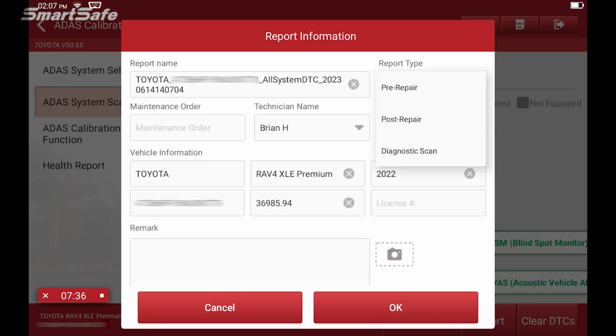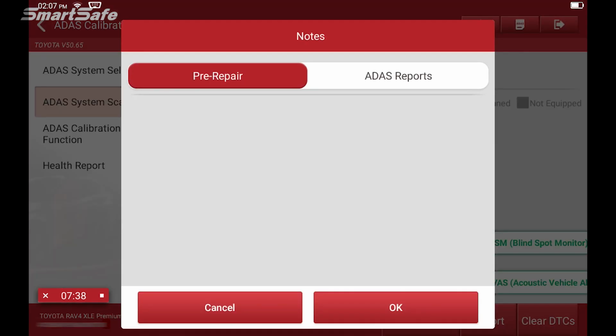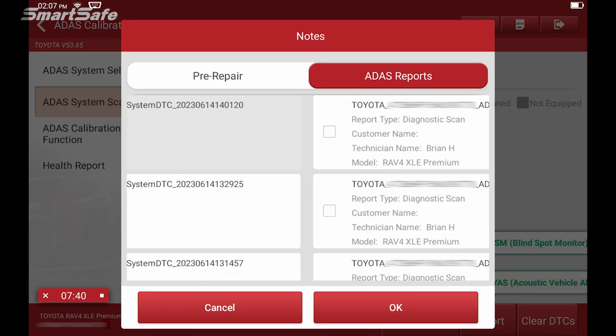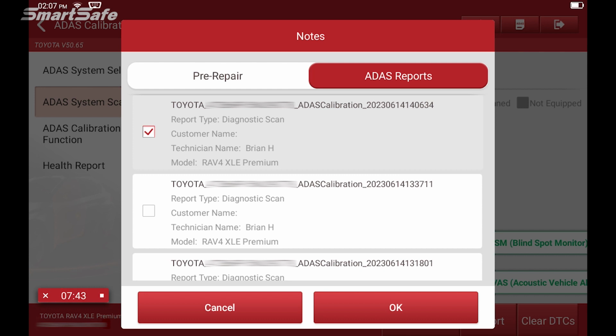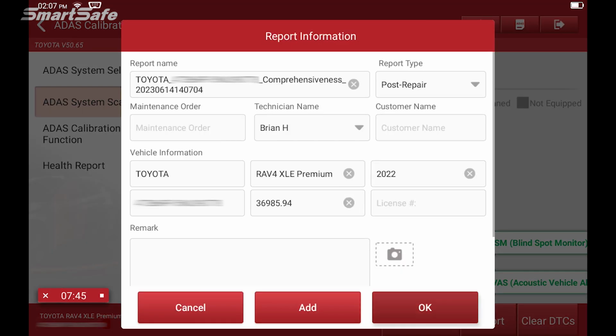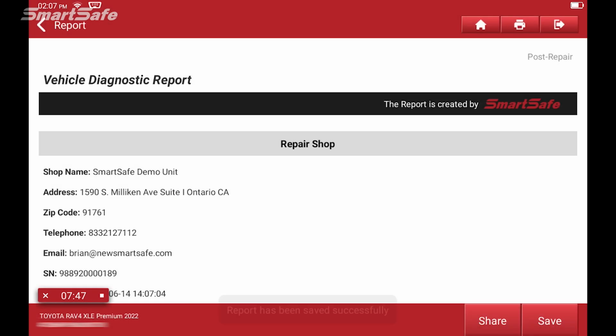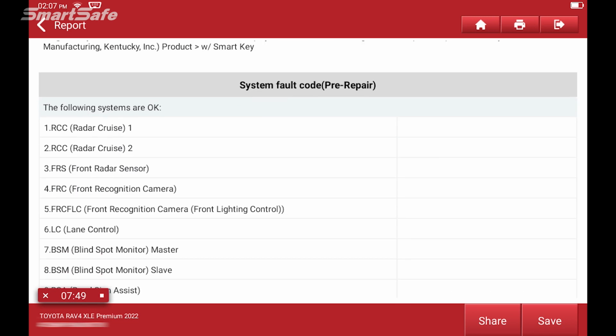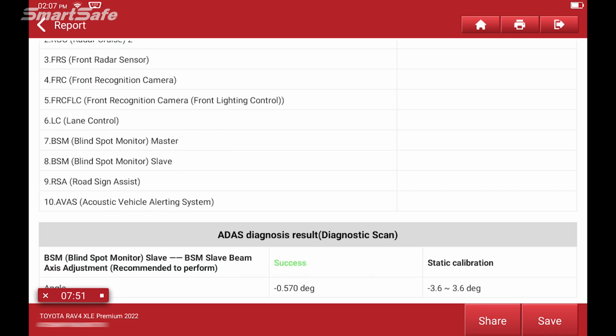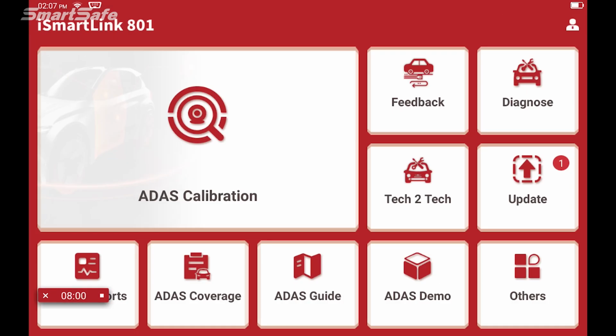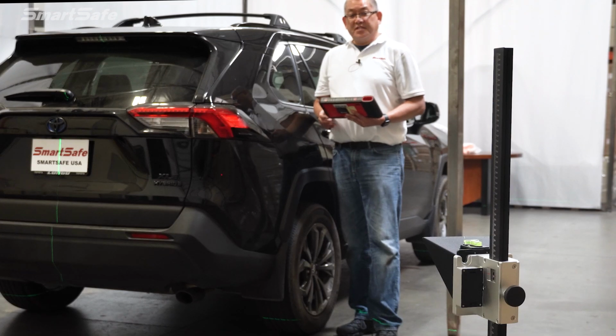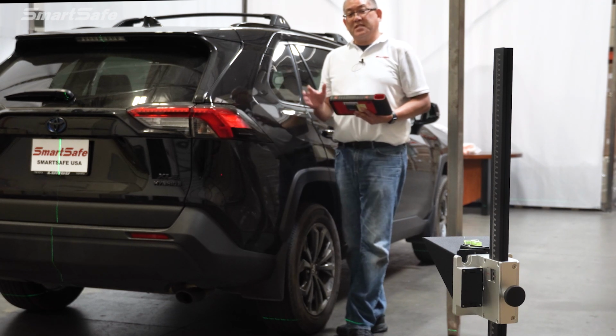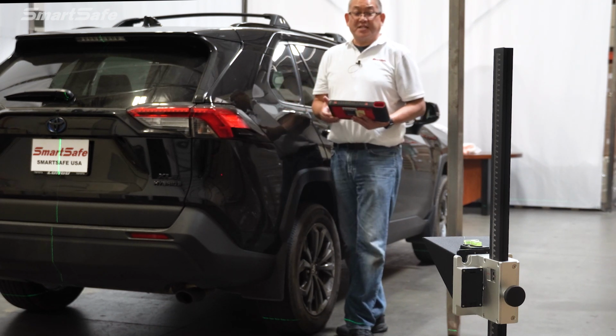We'll change our report type to post repair. We're going to add in our pre-repair as well as our diagnostic scan. Hit OK, OK. And now we have our post-repair report showing we have a successful static calibration of the blind spot monitor radar. So we'll save that, and then we'll go ahead and exit out. So this completes the calibration of the blind spot detection passenger side.